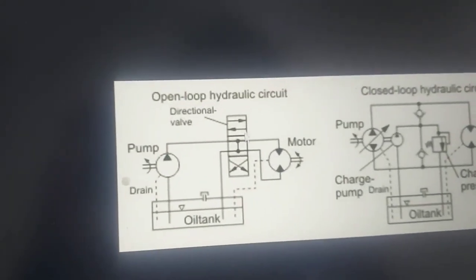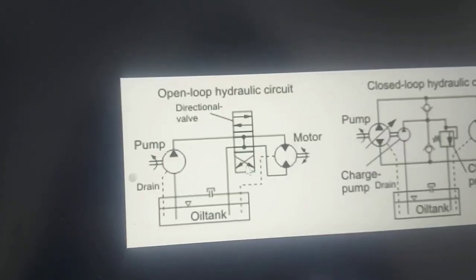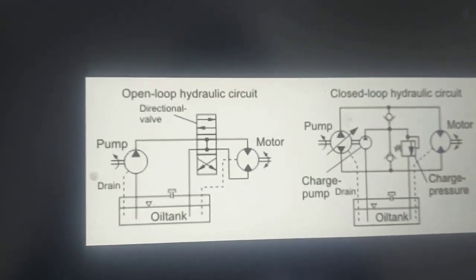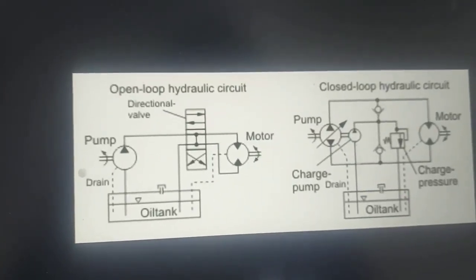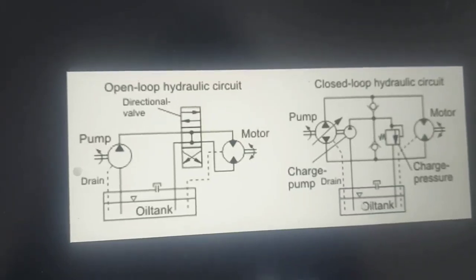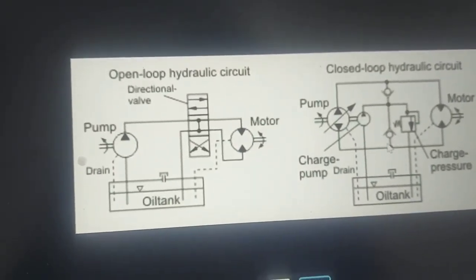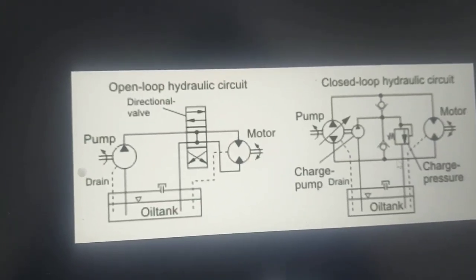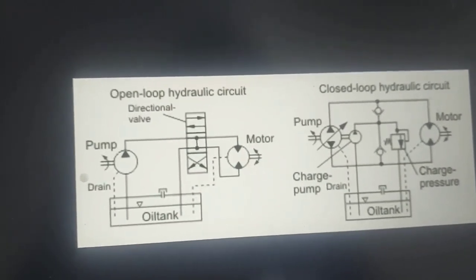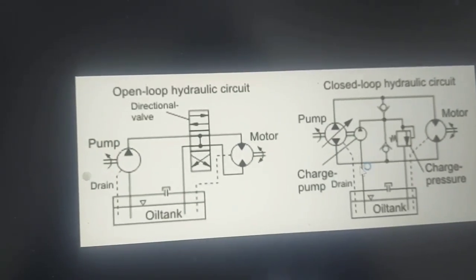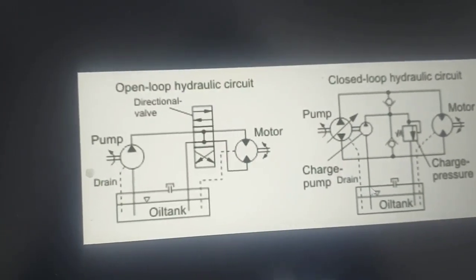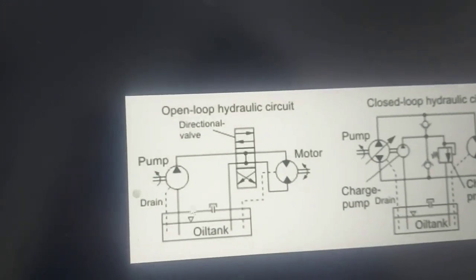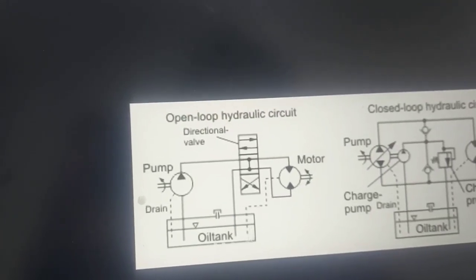In the open loop circuit, fresh oil always goes from the tank and all oil returns back to the tank. But in the closed loop circuit, the same oil circulates all the time — only the first fill comes from the tank. If there is leakage, it will draw a small quantity from the tank again. Because of this, in closed loop you can use a small tank like 50 to 100 liters, but in open loop you need a large tank of 300 to 400 liters.